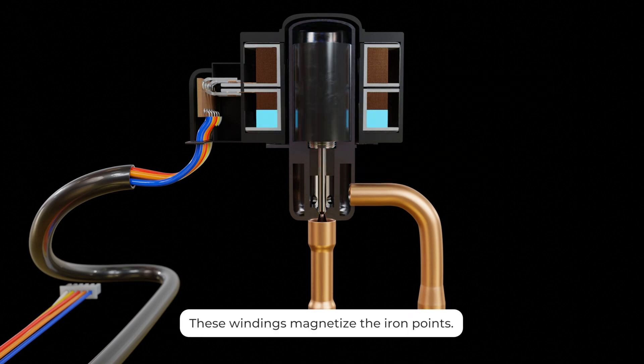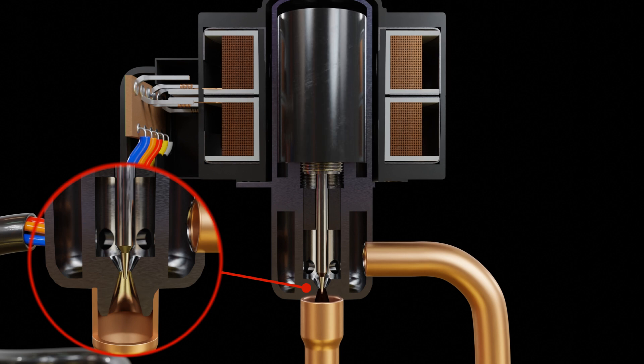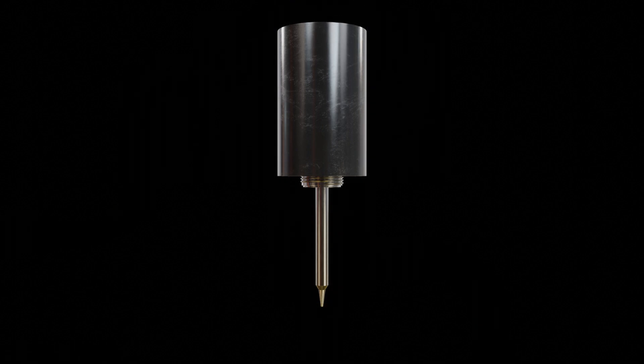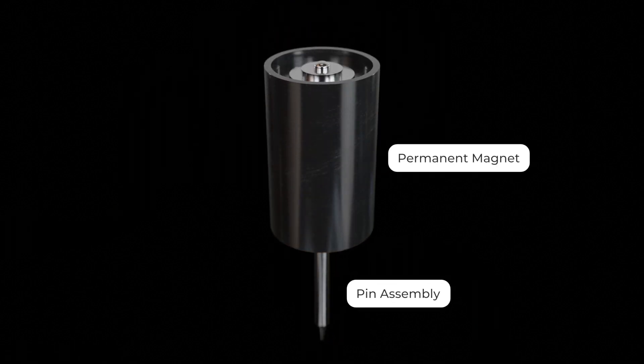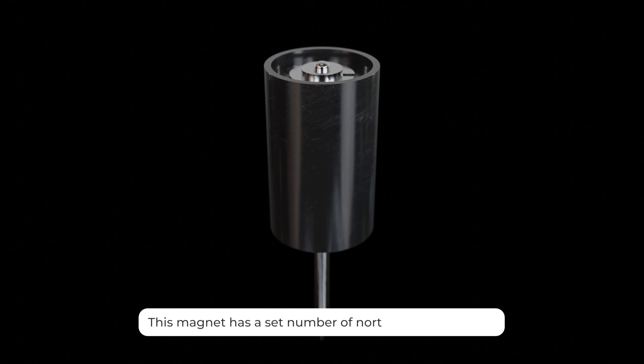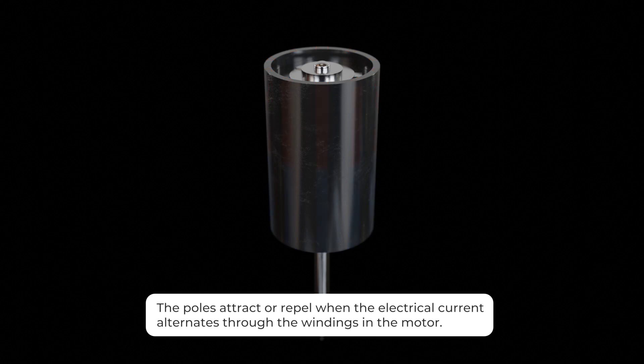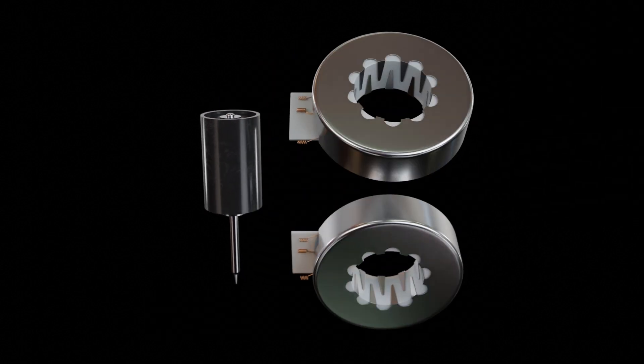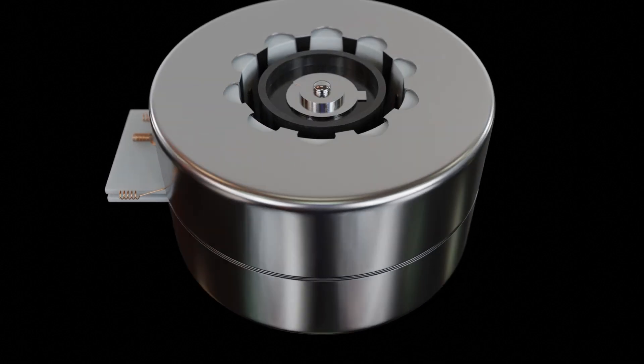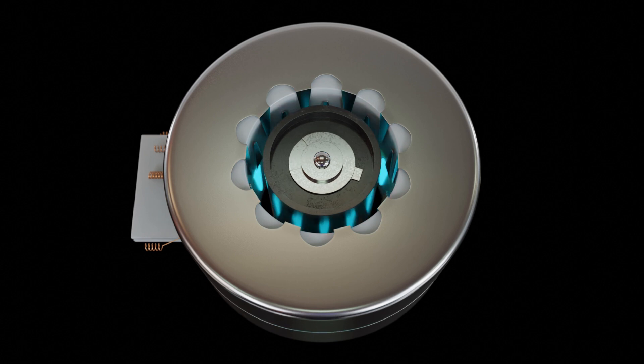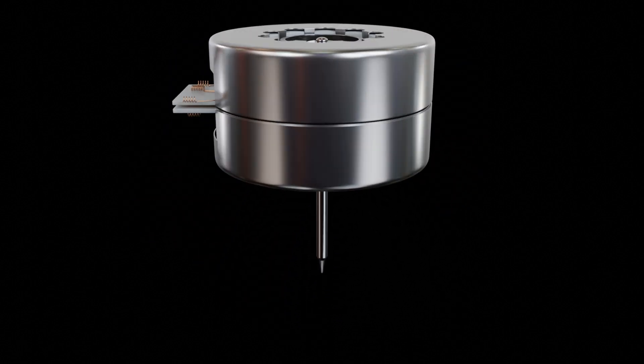These windings take in electrical signals and magnetize the iron points which help rotate a magnet connected to the inner rotor which moves up and down with clockwise and counterclockwise rotation. These EEVs have a permanent magnet inside an aluminum shell connected to the pin assembly. This magnet has a set number of north and south poles that attract or repel when the electrical current alternates through the windings in the motor.